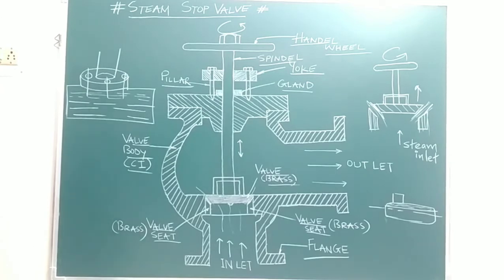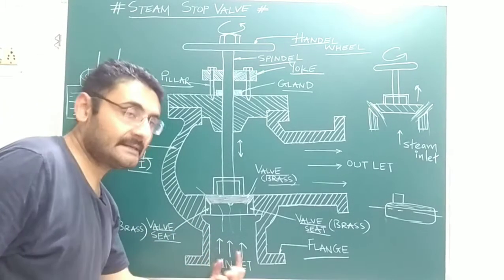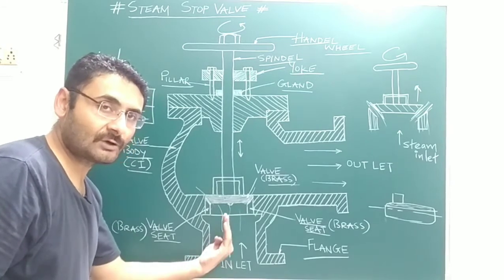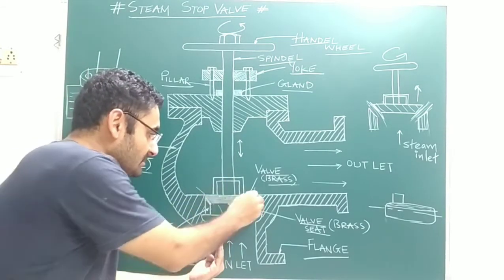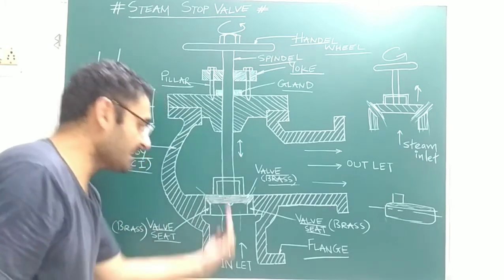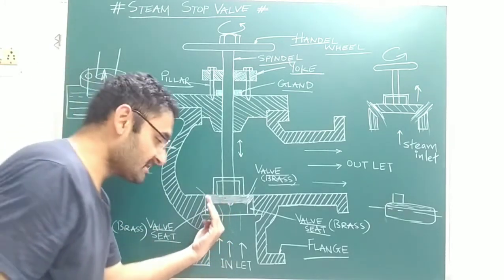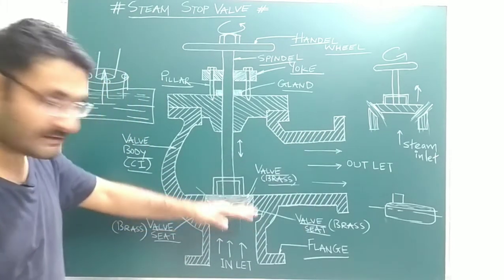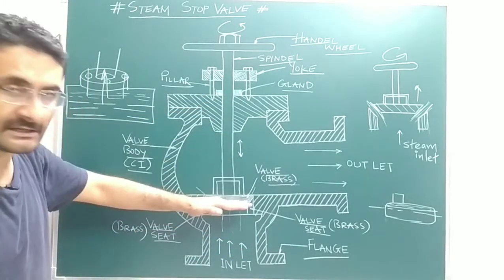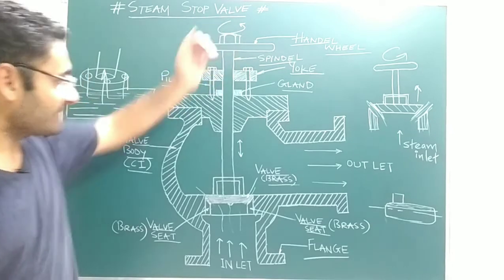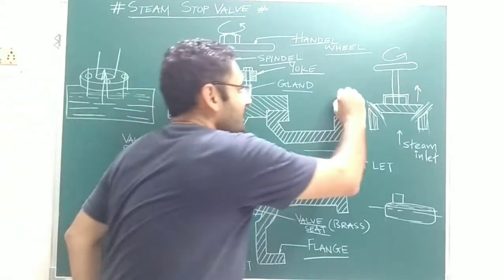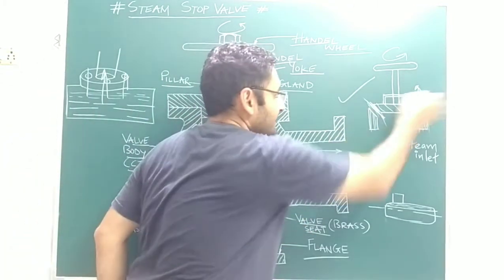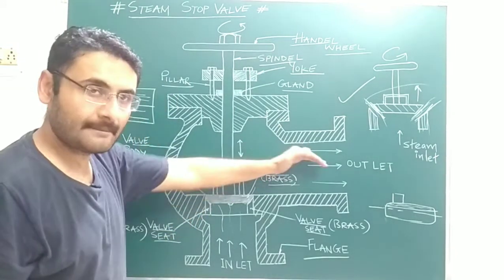Now for the working principle. When steam enters the steam stop valve from the inlet — which comes from the boiler — the valve is initially closed, so no passage is present. The steam stop valve does not allow the steam to escape; the steam remains inside the boiler. When you rotate the handle, the spindle moves upward, creating a passage between the valve seat and the valve.